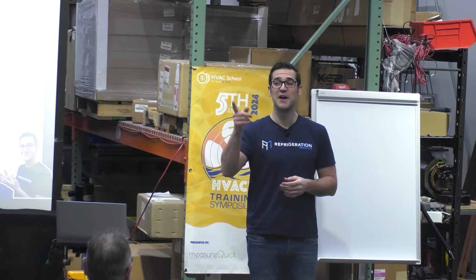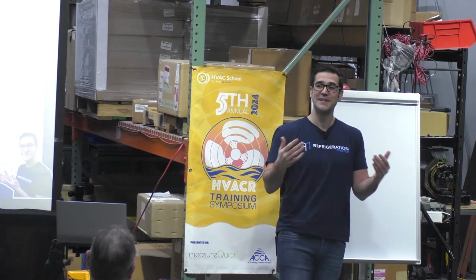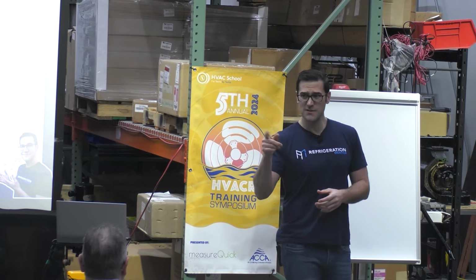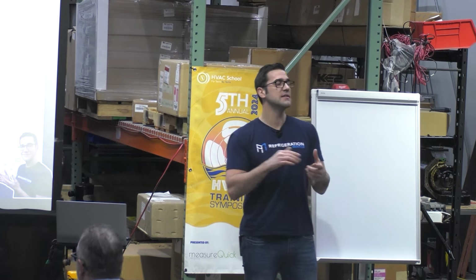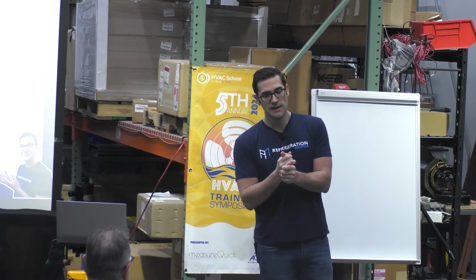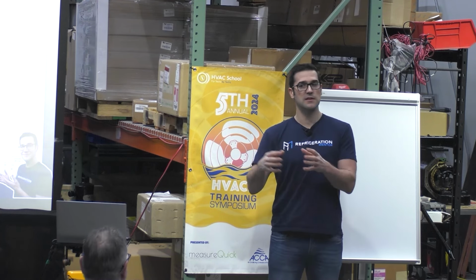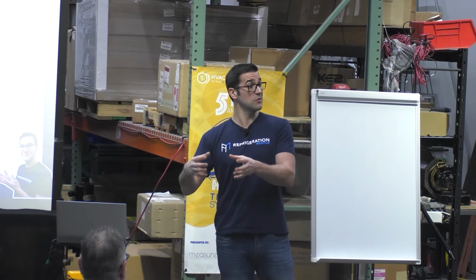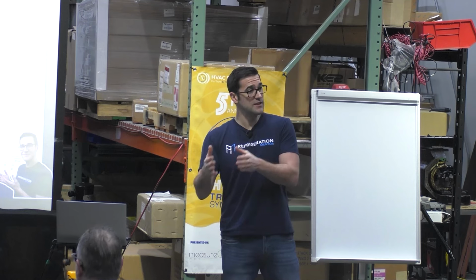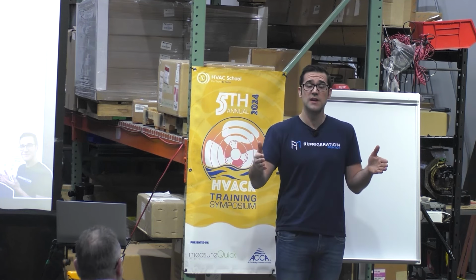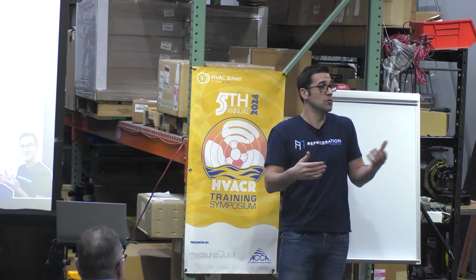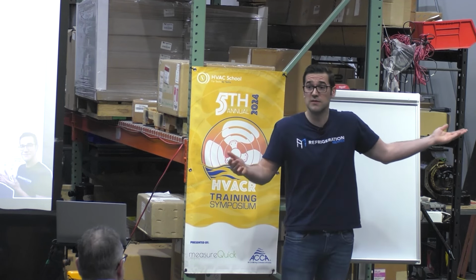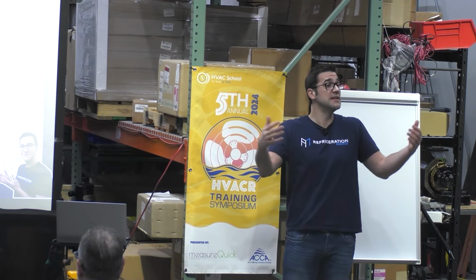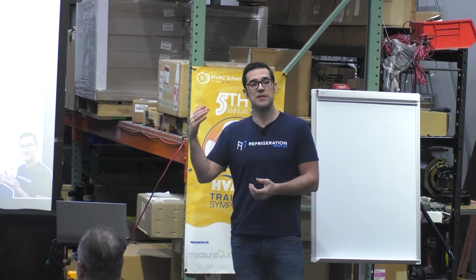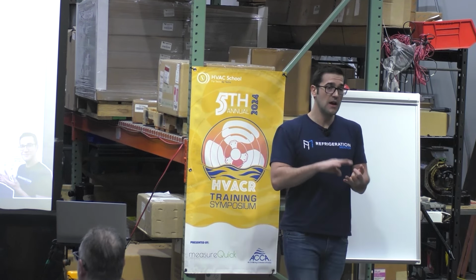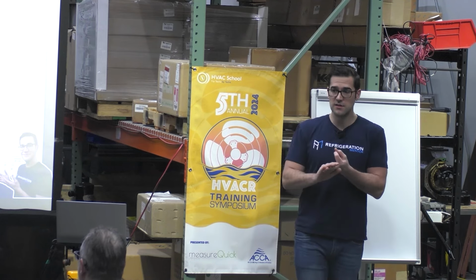One hand, because that was you guys, you were an original. That's the first thing that came out, right? Chris, right? Yeah. So the thing you want to understand is that it is a refrigerant. Is there safeties? 100%. When 410 came out, there was a lot of safety too. And there was that transition period, which took many, many years to get to the point where, okay, we put somebody in a truck, they go out and drive, and they just put gauges on the system. No big deal. It's going to be the same thing with these new refrigerants, A2Ls, A3s, and CO2.